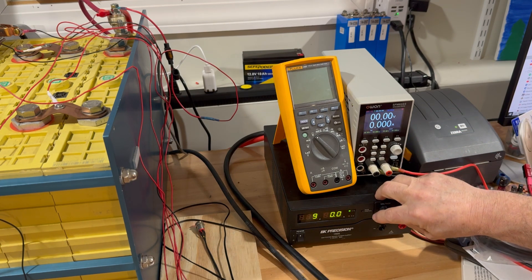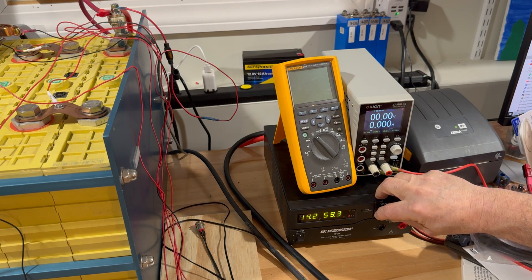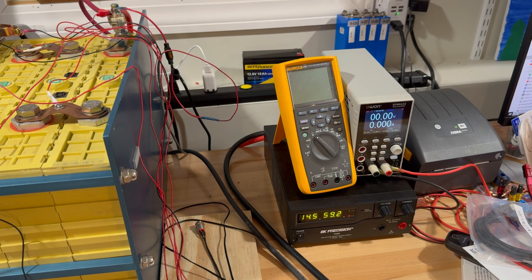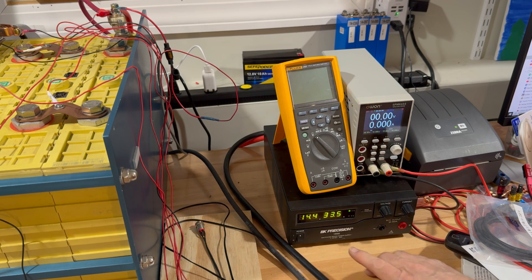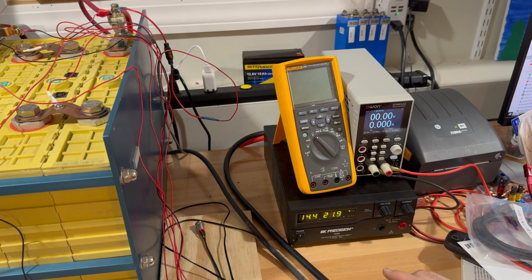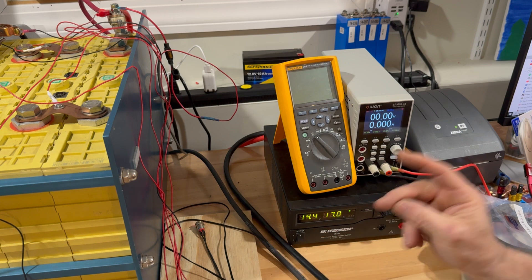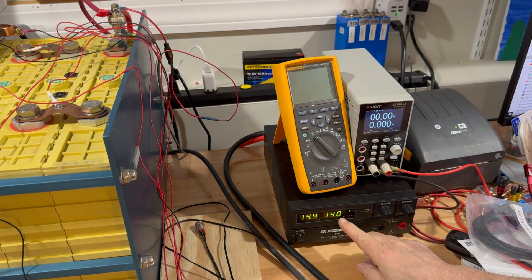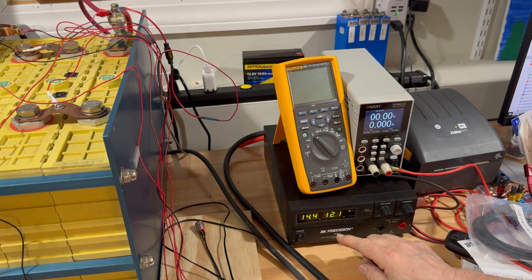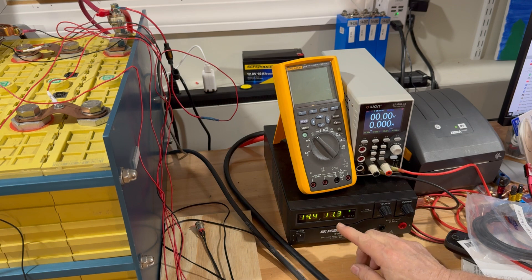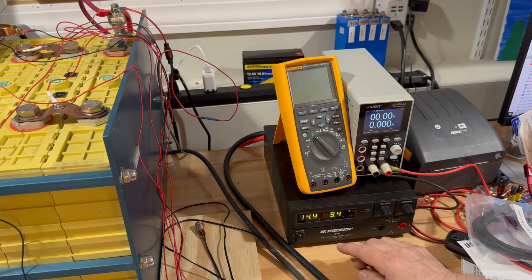Ready, I'm going to turn this up to 14.4. We can see that it's taking it for a few seconds. Now look at how fast that drops. That means it came up to 14.4 that fast. And now look at this, there's no current stored above 13.8, not much. This is maybe two tenths of an amp hour going into this battery.